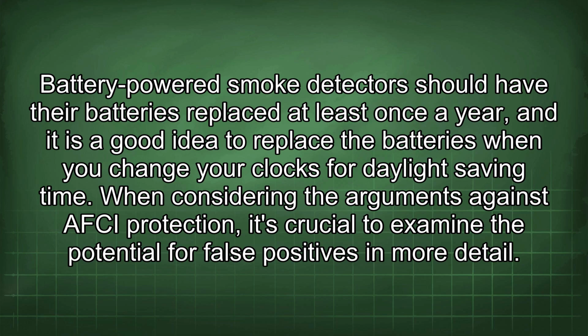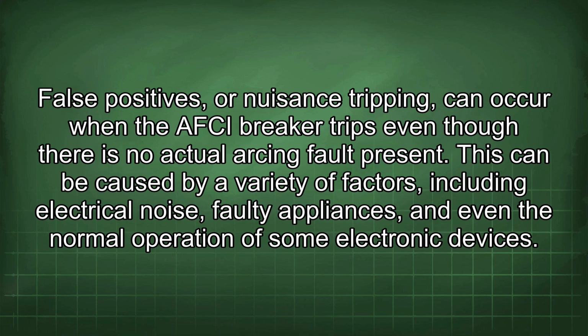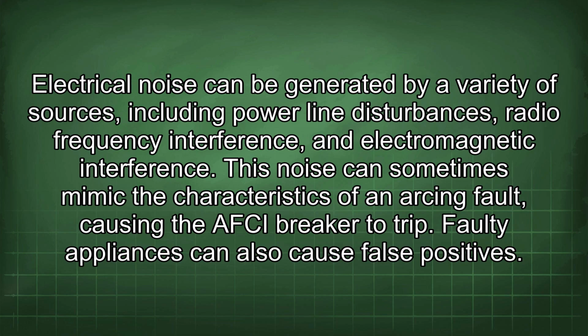When considering the arguments against AFCI protection, it's crucial to examine the potential for false positives in more detail. False positives, or nuisance tripping, can occur when the AFCI breaker trips even though there is no actual arcing fault present. This can be caused by a variety of factors, including electrical noise, faulty appliances, and even the normal operation of some electronic devices. Electrical noise can be generated by a variety of sources, including power line disturbances, radio frequency interference, and electromagnetic interference. This noise can sometimes mimic the characteristics of an arcing fault, causing the AFCI breaker to trip.